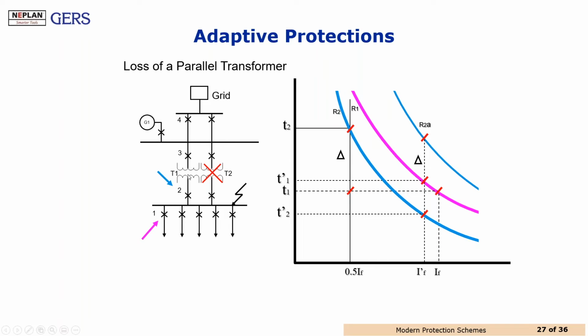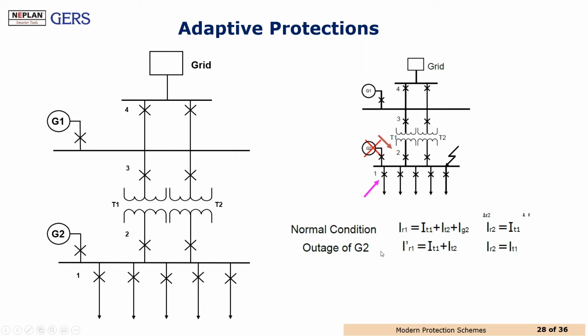We can see that in one state, we have the setting of relay number 2 in this part, but for the other state, the relay setting has changed. Well, and what happened with the distributed generation? Because that is something the same. If we have a new generator in this part, in normal conditions the fault current will consider the current from the generator plus the current from transformers T1 and T2. But if we don't have the generator, the current is reduced. Why? Because in this case, this short circuit contribution is not considered.